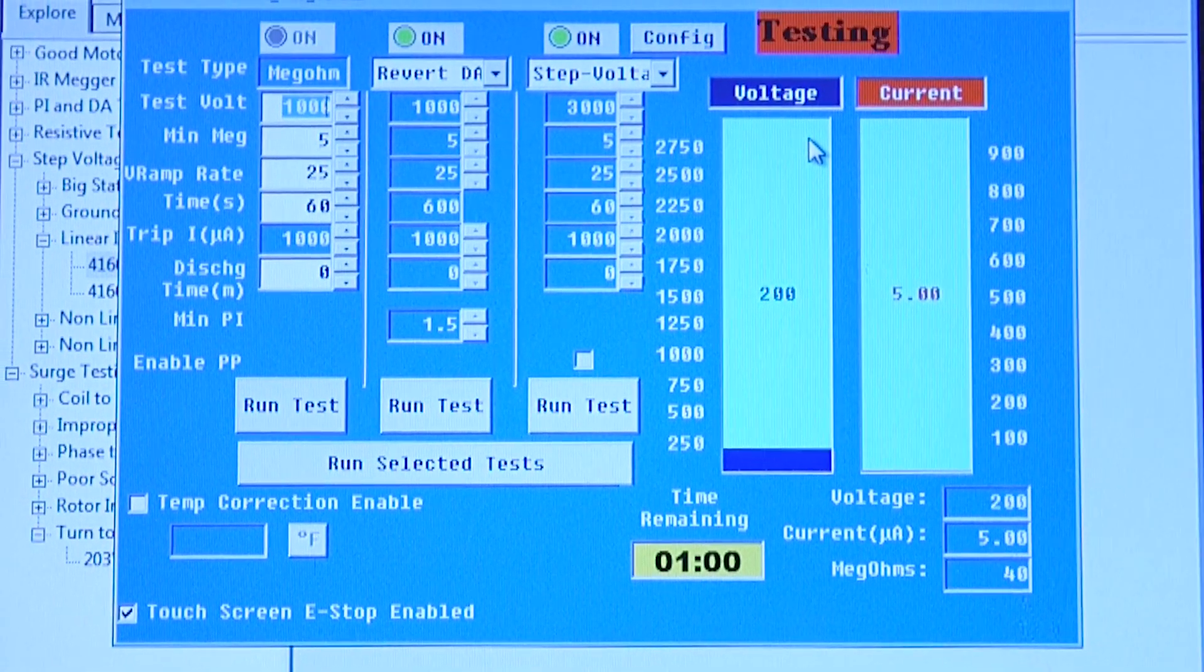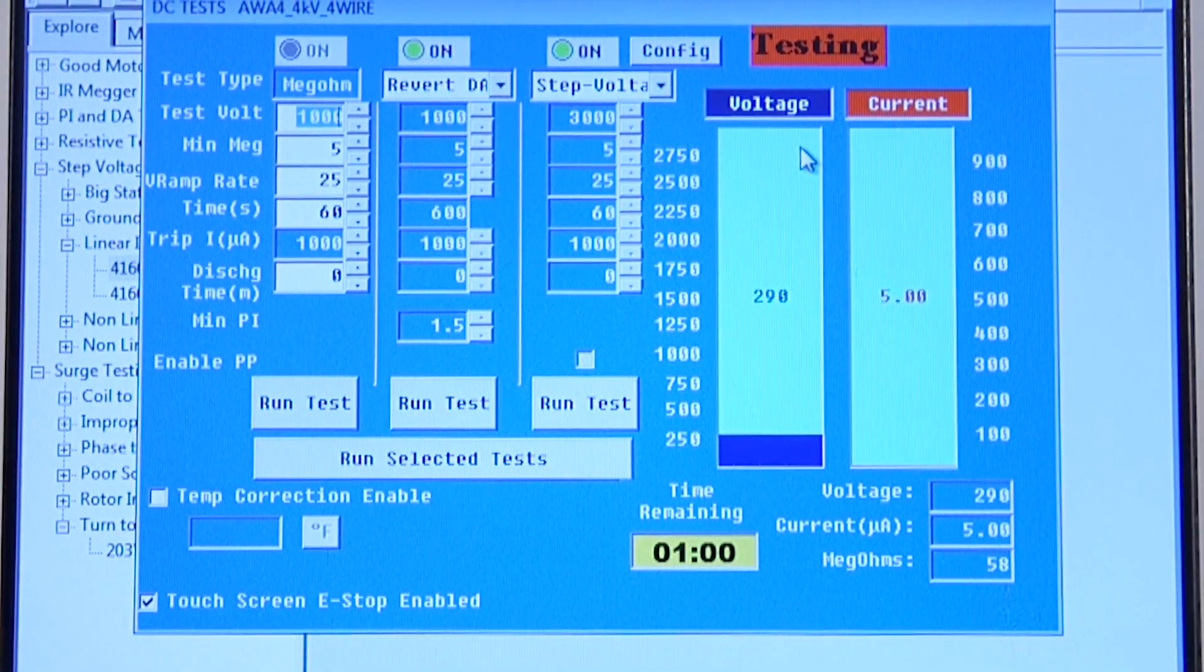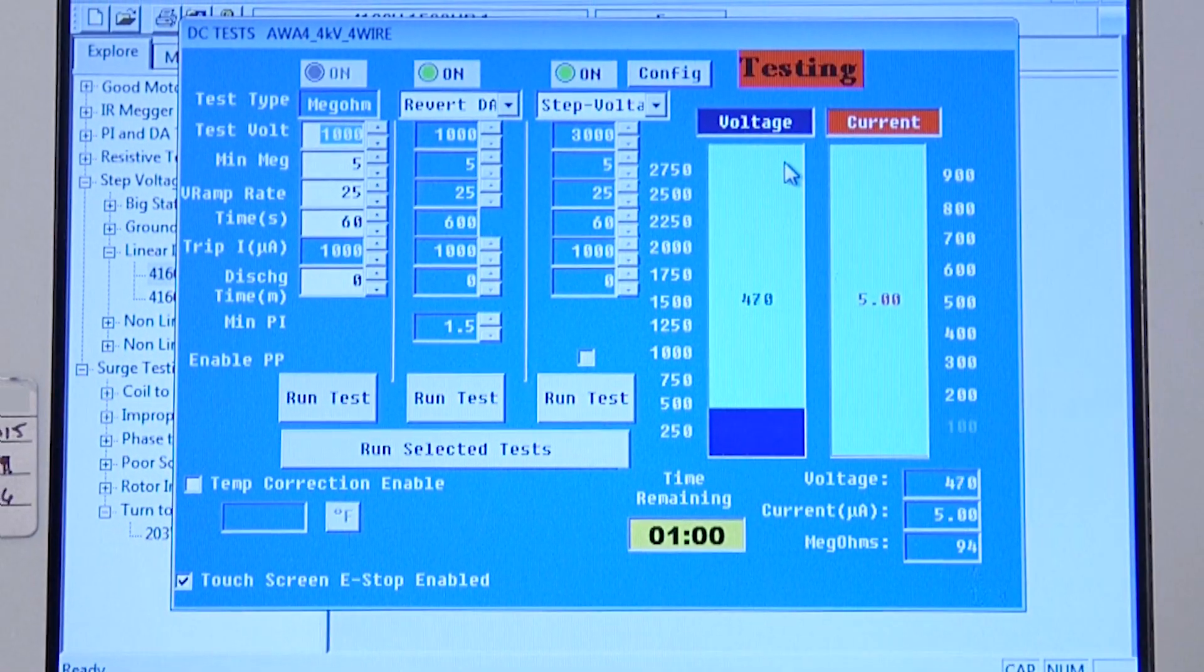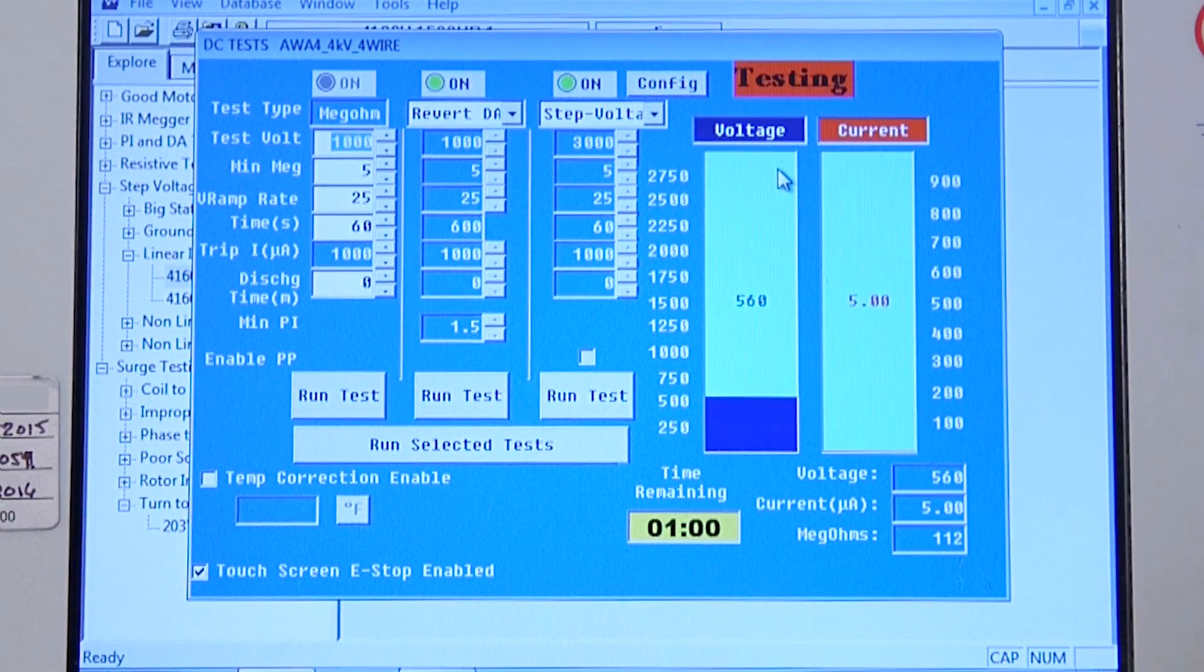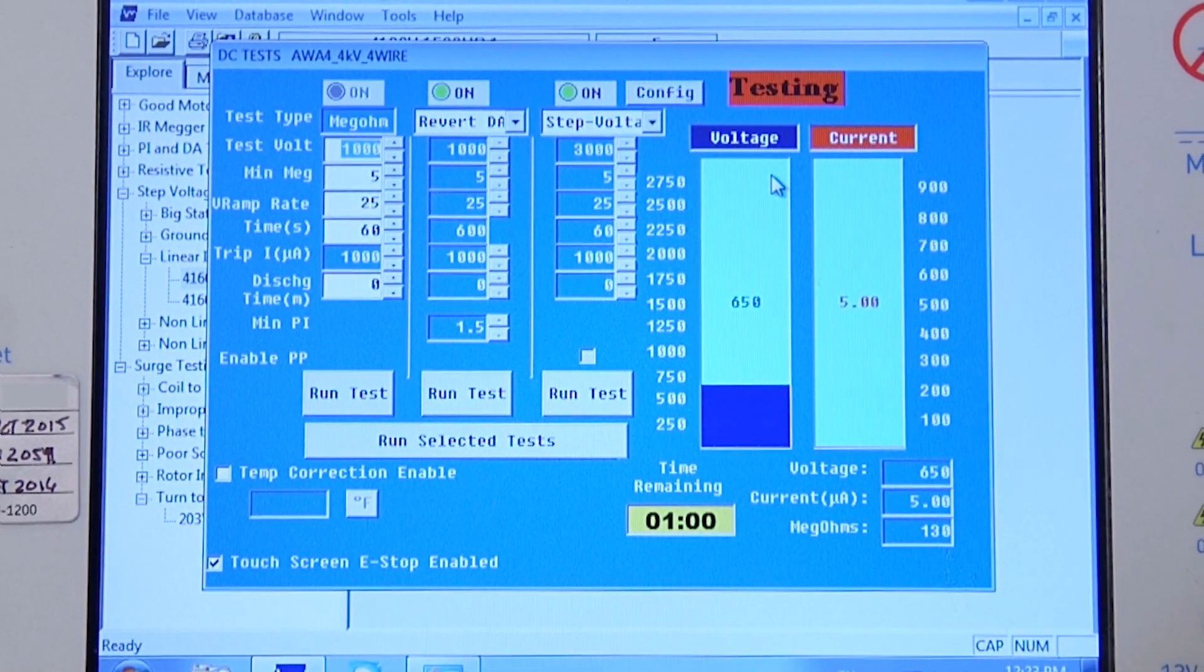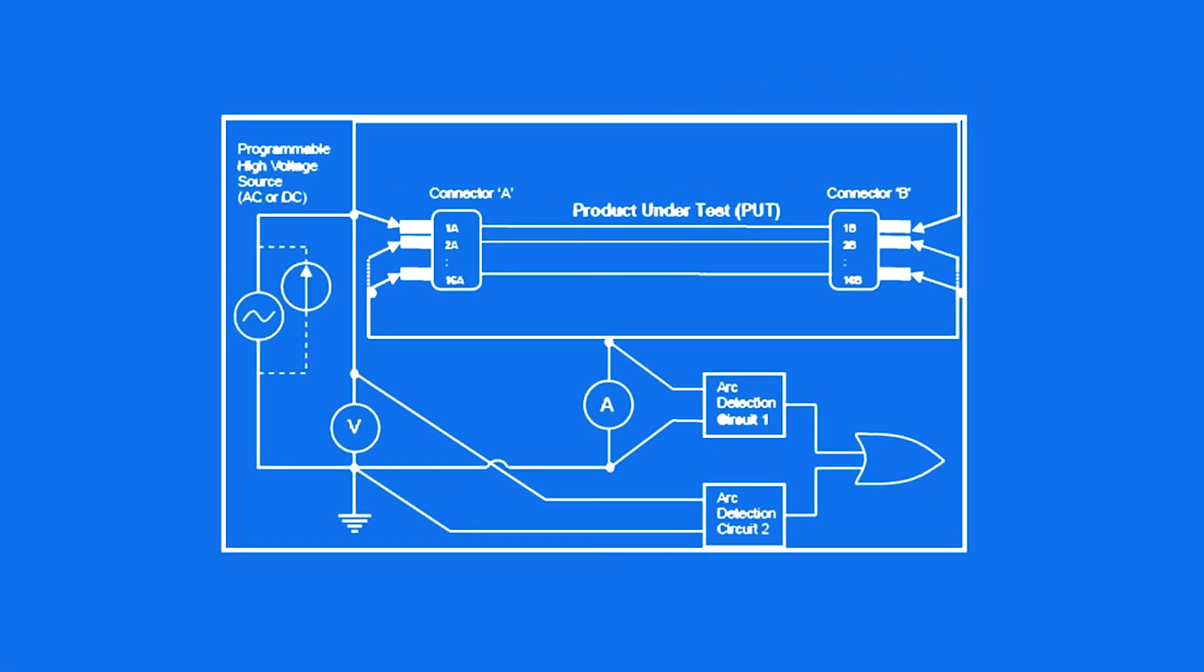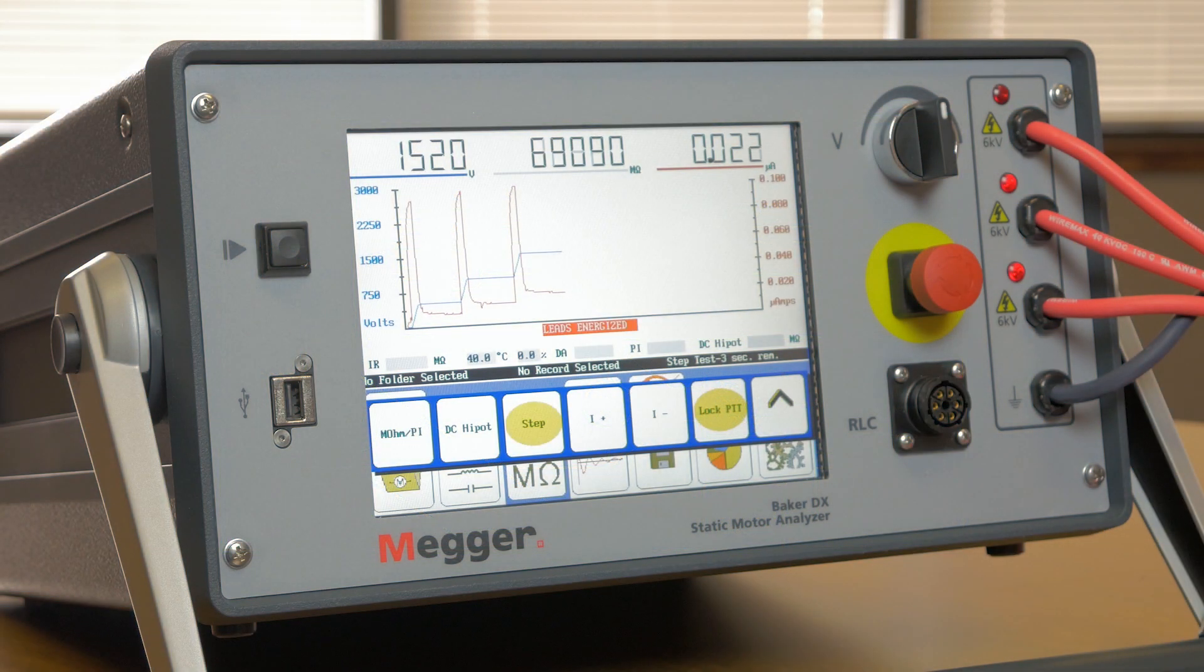A mega-test or mega-ohm test typically tests the ground-wall insulation at or below the motor operating voltage. This has limited value as insulation breaks down non-linearly as the voltage increases. A high-pot test is a DC ground-wall insulation test but run at higher voltage. This covers the peak voltages a motor would normally see with some level of margin.